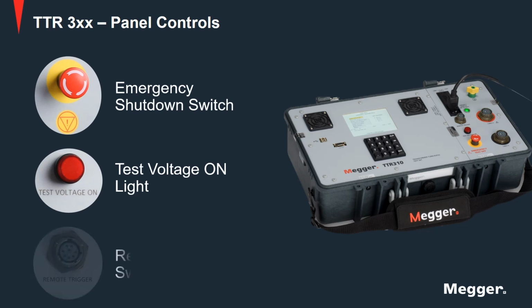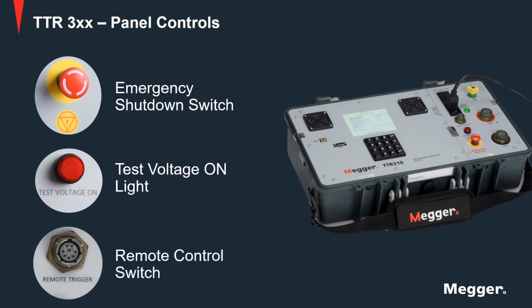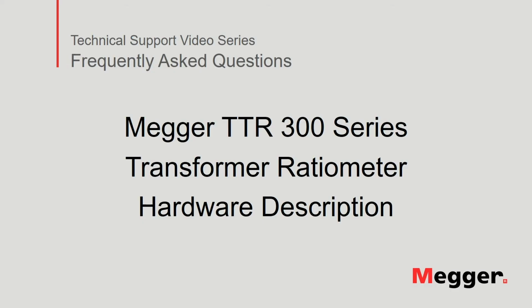Lastly, we have the remote control switch. This switch is primarily used when testing on-load tap changers and de-energized tap changers of a transformer. The remote control switch can remotely start the TTR test and store multiple ratio readings for tap changers. The storage function in remote mode is sequential and occurs during a continuous ratio test.